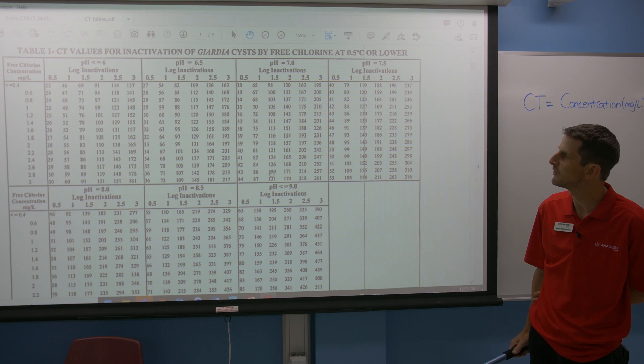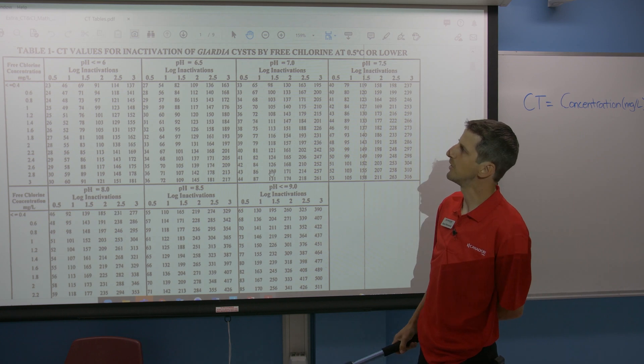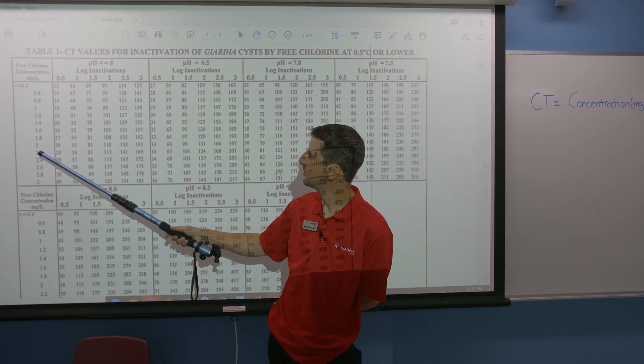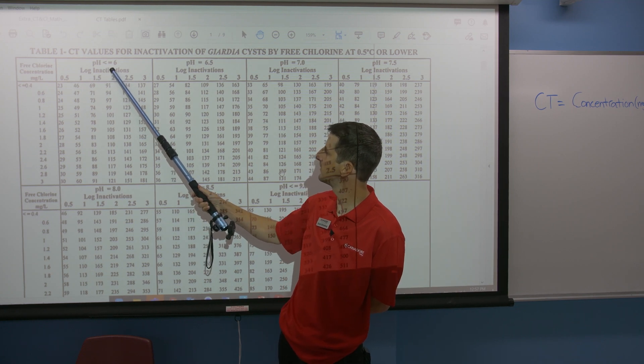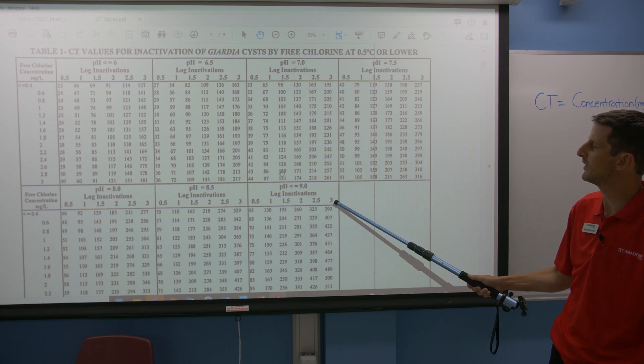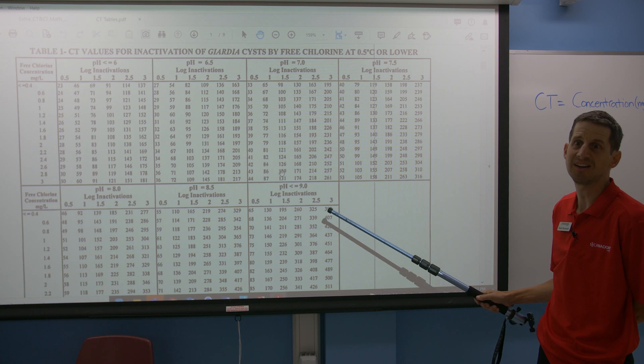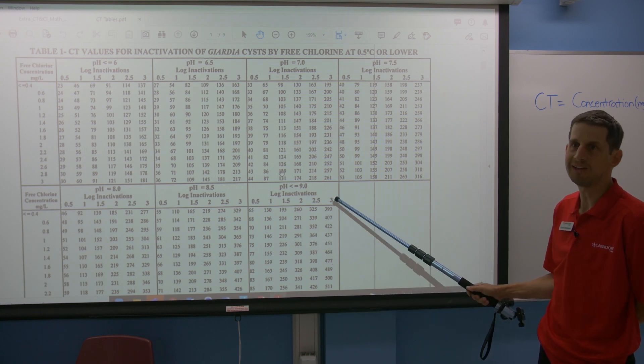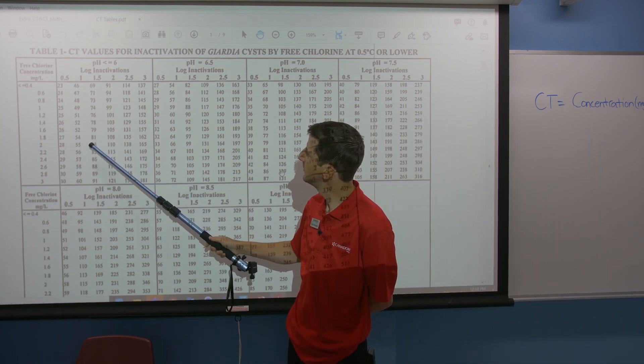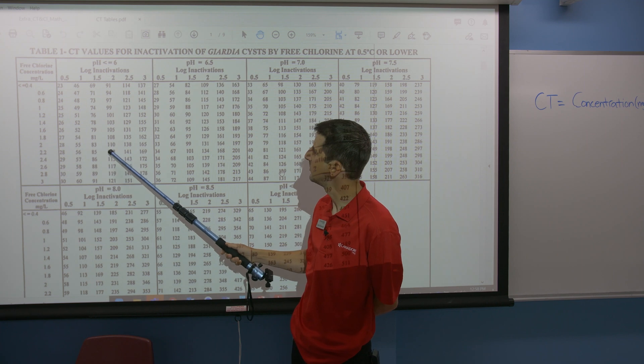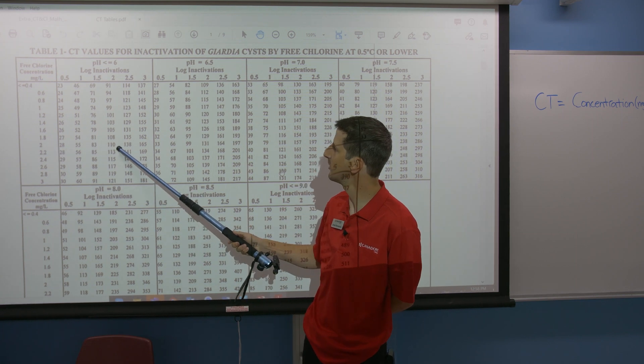One trend to notice here — keeping temperature controlled — is the effect of pH. Let's look at a concentration of 2 milligrams per liter. The first column is pH less than or equal to 6, and at the far end of the spectrum, pH less than or equal to 9. If we ask ourselves whether disinfection by chlorine is more effective at a higher or lower pH, we can find that trend in the table. At pH less than 6, the CT value for 2-log inactivation at 2 mg/L concentration is 110.